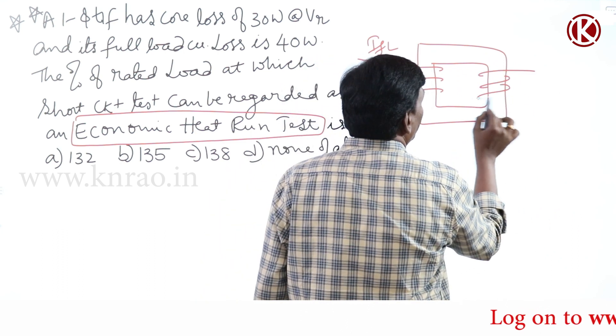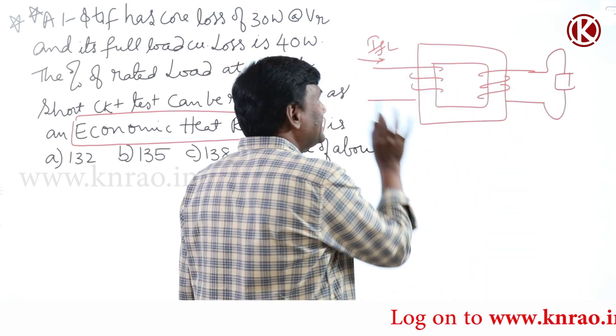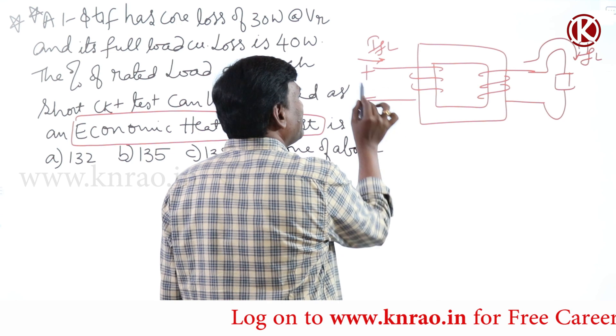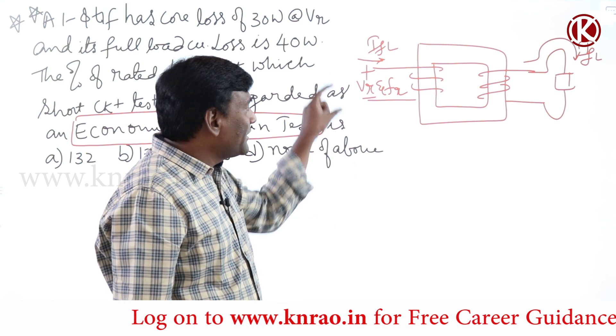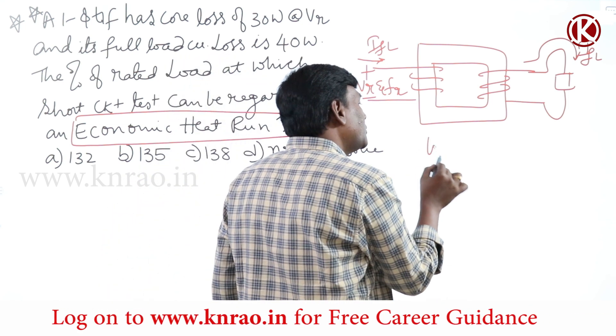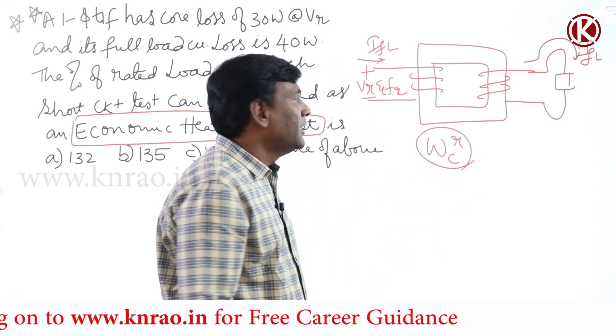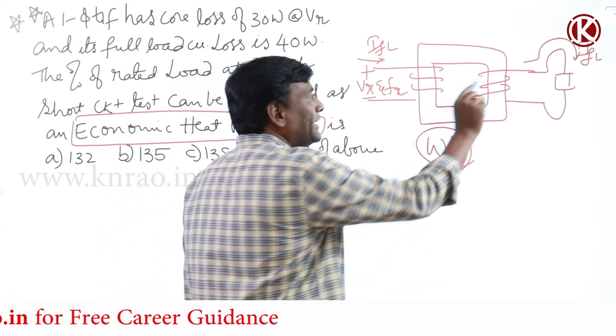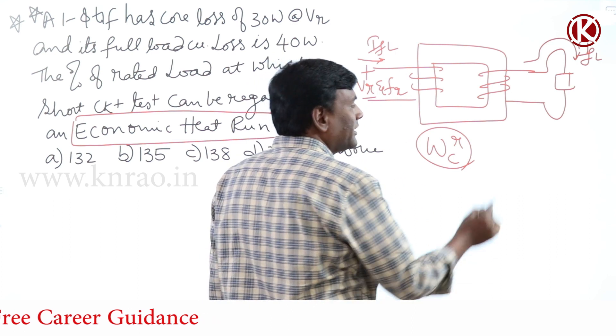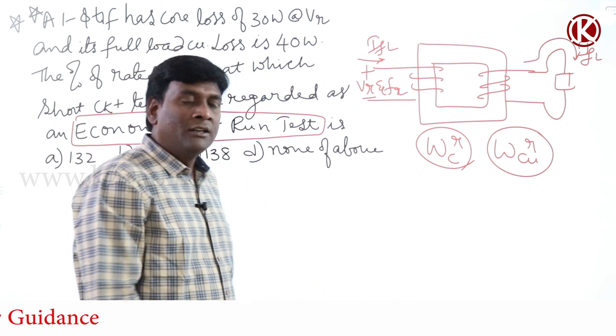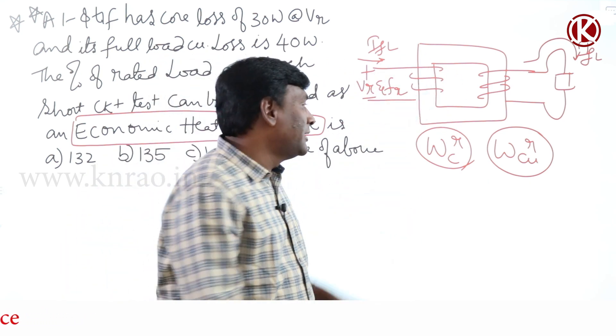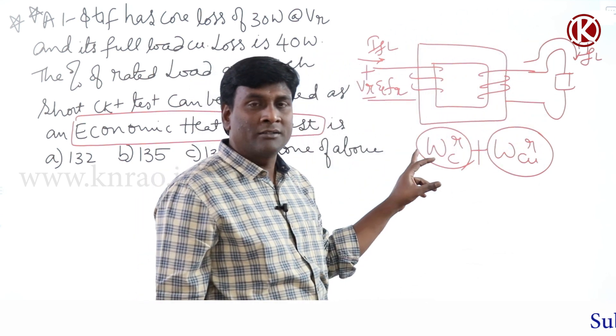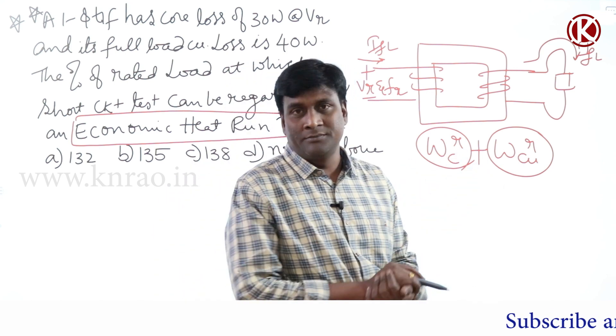In a practical transformer operating at full load conditions, if I supply rated voltage and rated frequency, core losses are going to be rated. If I connect my rated load, rated current will flow — my copper winding will be fully utilized. So rated current flows, copper losses are also rated. Temperature rise in a practical transformer is decided by both core loss and copper loss combined.